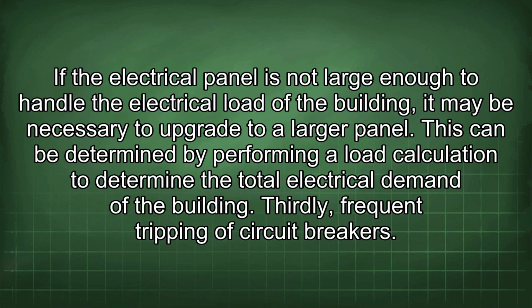Secondly, insufficient capacity. If the electrical panel is not large enough to handle the electrical load of the building, it may be necessary to upgrade to a larger panel. This can be determined by performing a load calculation to determine the total electrical demand of the building.